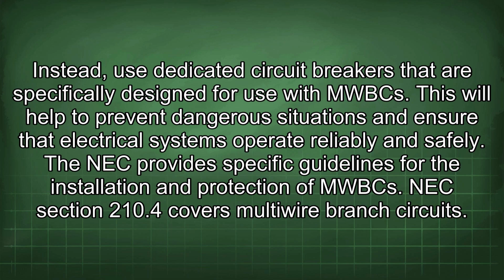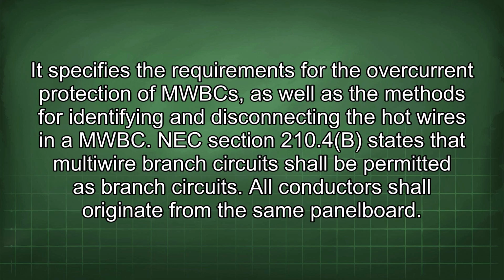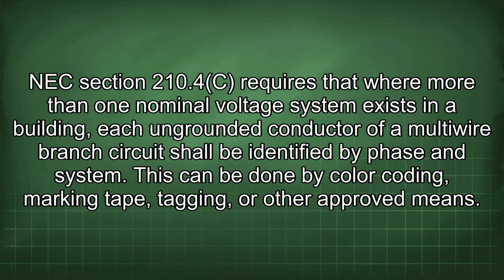NEC Section 210.4 covers multi-wire branch circuits. It specifies the requirements for the overcurrent protection of MWBCs, as well as the methods for identifying and disconnecting the hot wires in MWBC. NEC Section 210.4b states that multi-wire branch circuits shall be permitted as branch circuits. All conductors shall originate from the same panel board. NEC Section 210.4c requires that where more than one nominal voltage system exists in a building, each ungrounded conductor of a multi-wire branch circuit shall be identified by phase and system. This can be done by color coding, marking tape, tagging, or other approved means.